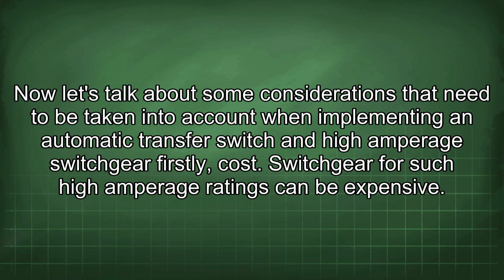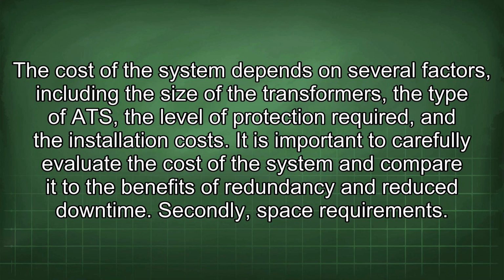Firstly, cost. Switchgear for such high amperage ratings can be expensive. The cost of the system depends on several factors, including the size of the transformers, the type of ATS, the level of protection required, and the installation costs. It is important to carefully evaluate the cost of the system and compare it to the benefits of redundancy and reduced downtime. Secondly, space requirements.